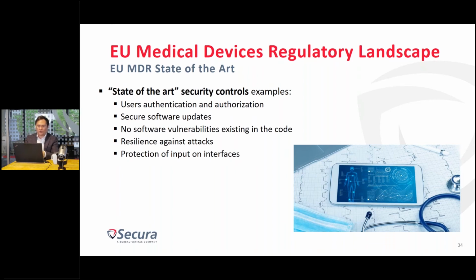Also role separation, security of software updates, the capacity of the device to check for software vulnerabilities and ensure there are none existing in its code, and also things such as resilience against attacks or protection on the interfaces, whether wired or wireless. So those are the main directions in which state-of-the-art should be understood by medical device manufacturers.